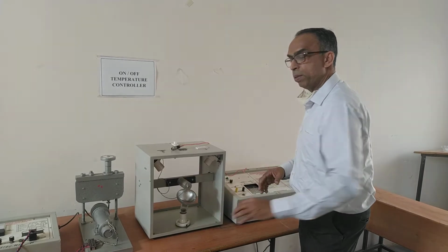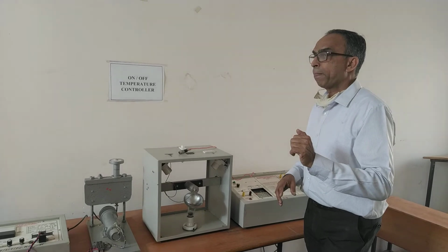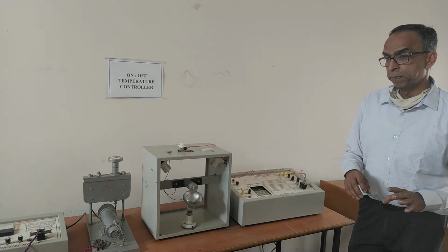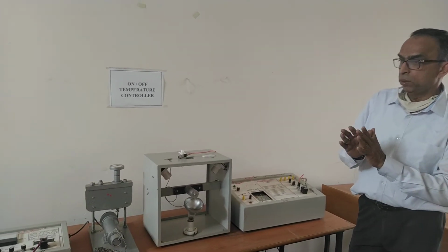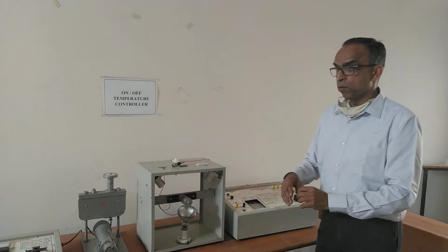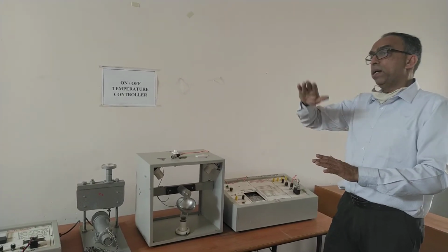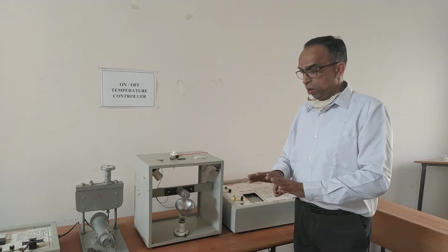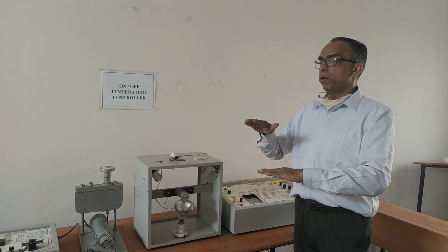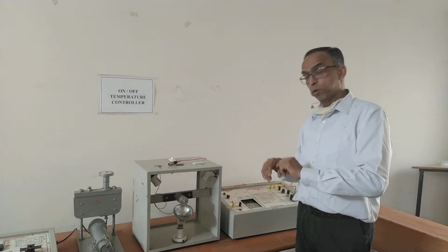The temperature of this bar will be suddenly affected. Because of this sudden load change, as we said, the proportional controller has a tendency to generate an offset. What do you mean by this offset? My original set point was 100 degrees Celsius. Because of this sudden load change, the proportional controller will shift its set point to 120 degrees Celsius on its own. So my original set point was 100 degrees Celsius, and now the changed set point is 120 degrees Celsius. This 20 degrees is the offset of this proportional controller.